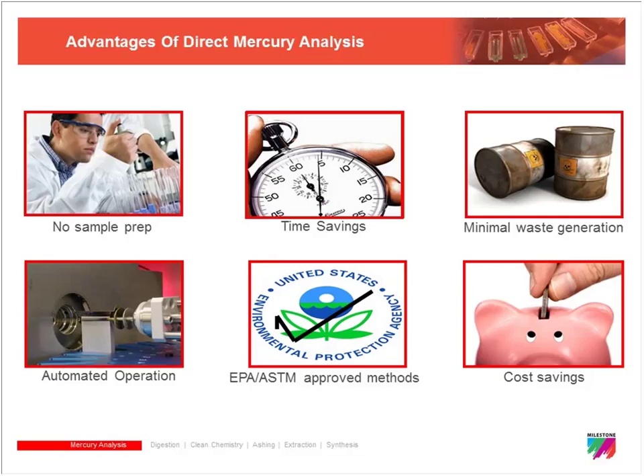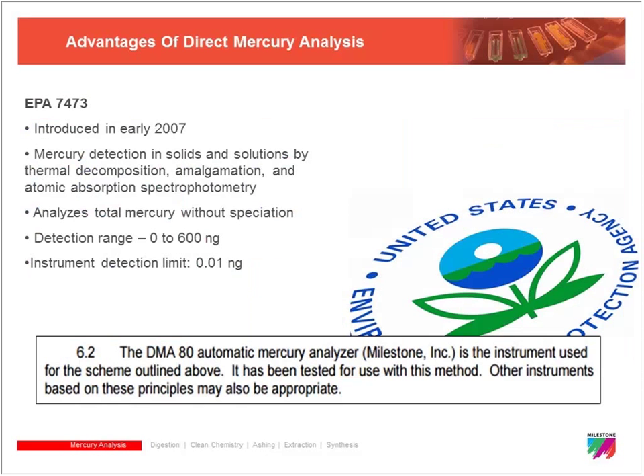As I mentioned earlier before, we were fortunate enough to have been referenced in an EPA method. So there's an EPA method approved for the direct analysis of mercury in solids and waters, aqueous solutions. This method is EPA 7473, introduced in early 2007, so it's the thermal decomposition and amalgamation and analysis by atomic absorption spectrophotometry. The detection range is 0 to 600 nanograms with a detection limit of 0.01 nanograms. So for any labs that are looking to comply with any EPA methods, there is an approved method for the use of a direct mercury analyzer.